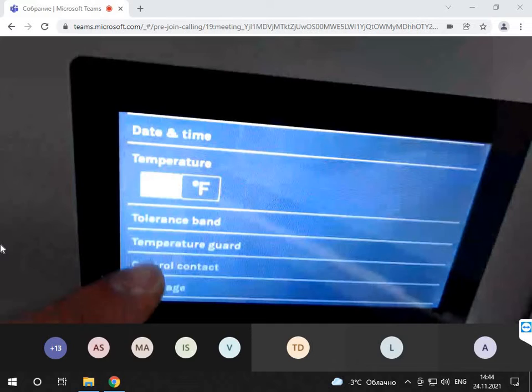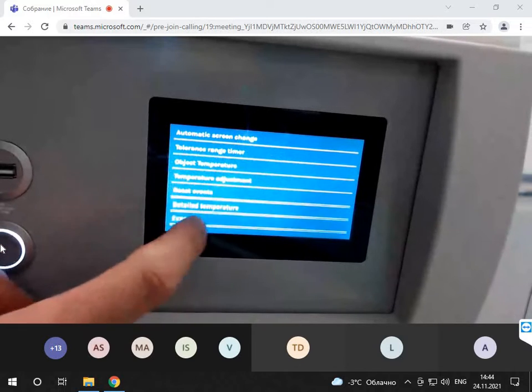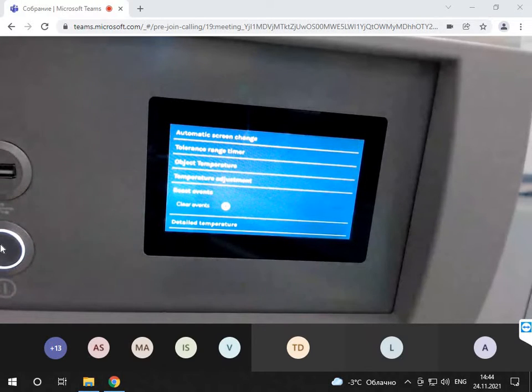So, in case of an error, firstly, what do you do? The first important step is to reset events. If you have an error message, please reset the events first, because the HMI, the touch panel, stores the last error message and usually always shows you the error message. Clear the events to be sure that all is clear, and if the error message occurs after clearing the events, maybe one part is defective. That's the first step.